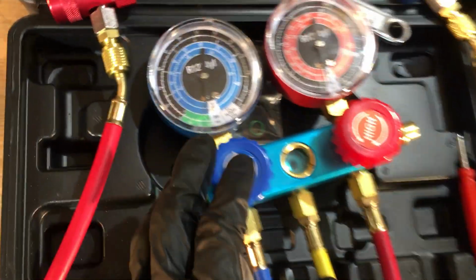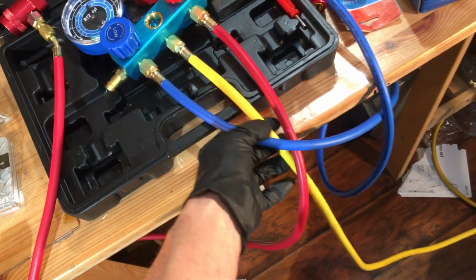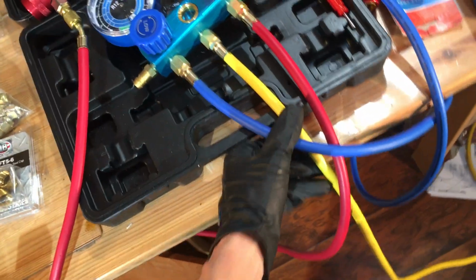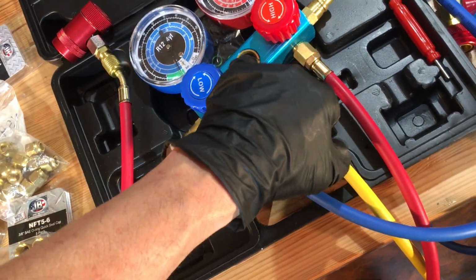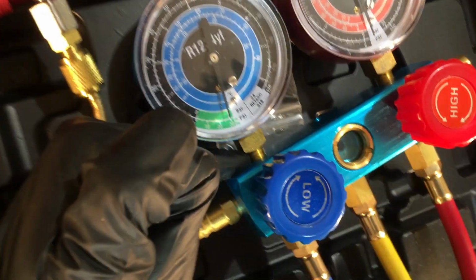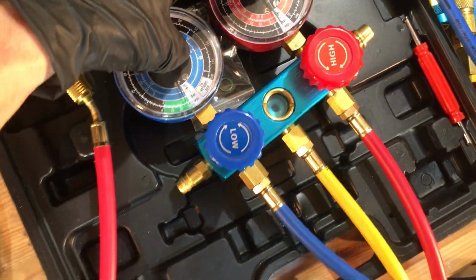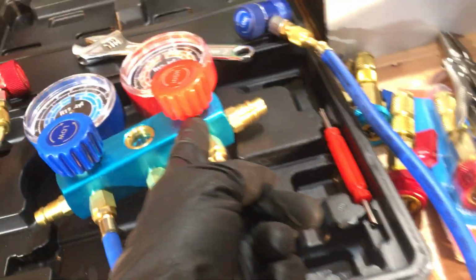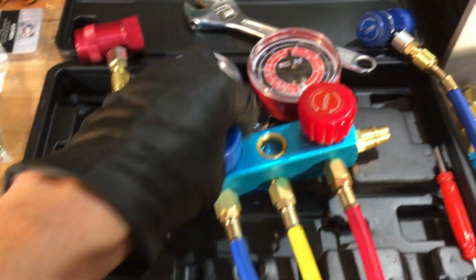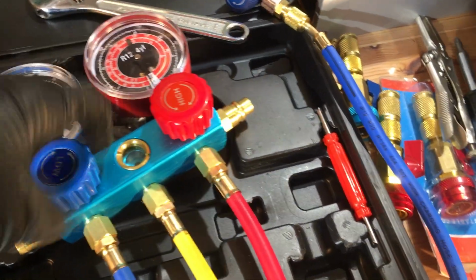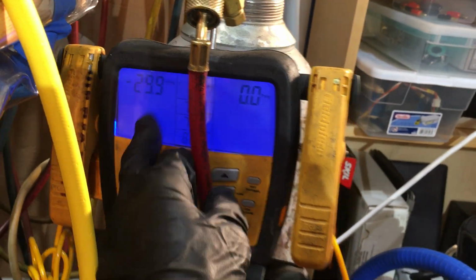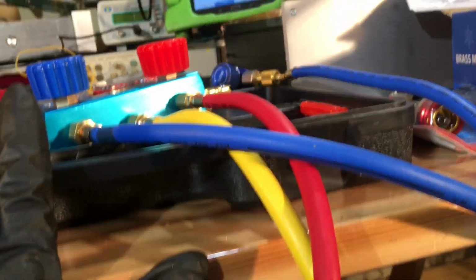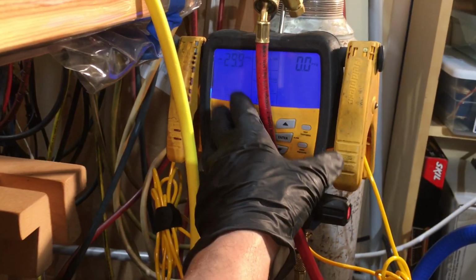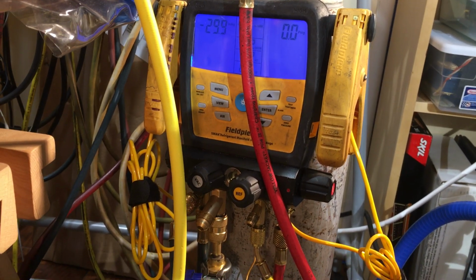And if we come back to our gauge set, we're at 29. These brand new hoses and everything are so saturated with moisture, and probably a little leakage. It could come through here. Your leakage could come from these threads right here. They could come from inside cheap gauges. These shafts have seals on them. Leakage could come from these. So you could have leaks there. And we come back over and we're still at 29.9. But we failed the vacuum test because we could not hold it down below 500 microns.